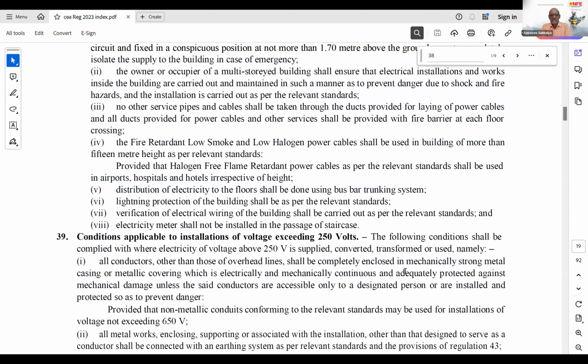Thank you, Mr. Abhijeet. So, as you said, people in a massive fire do not die of electrocution. They die due to the smoke that engulfs. So, where do these toxic smokes come from? Primarily from cables. So, every possibility of avoiding the cables would be a solution. That's why the regulation provides for making use of the bus bar trunking system. That bus bar trunking is not meant for the major transformer to main panel or generator to main panel. It is specifically for the floors. They have specifically stated for the floors.